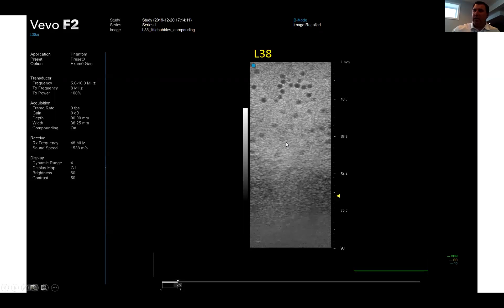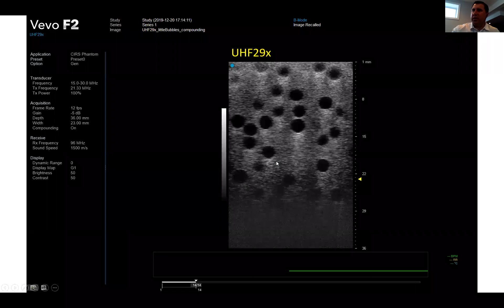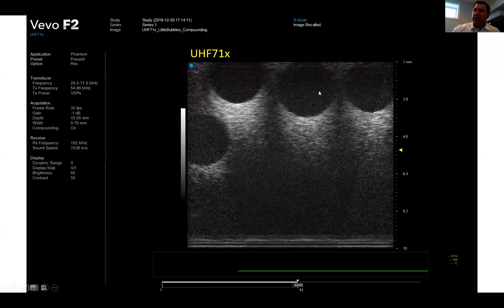As we start moving up in frequency now, you see what happens as we go from 15 to 30. So we've got a center here around 21 megahertz, and you start to see these spheres, which are on the order of a few millimeters in diameter, with much more clarity and better contrast resolution. And finally, if we go all the way up, here we've got these very small spheres that are showing up quite large. These are now doing this at 70 megahertz.